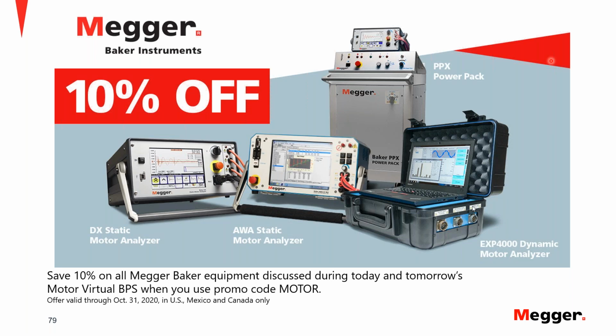So Abel actually was trying to focus mostly on the tests that directly evaluate insulation life. I know our manual does have in it, and the AWA actually, that the first test you'll encounter is the resistance test. So what does the resistance test do for us? Again, it's part of the low voltage testing group for static testing. We have a resistance test and the meg test, the PI, DA are all low voltage tests, considered low voltage because they are done at or near nameplate voltage. And it is good to do that test first.